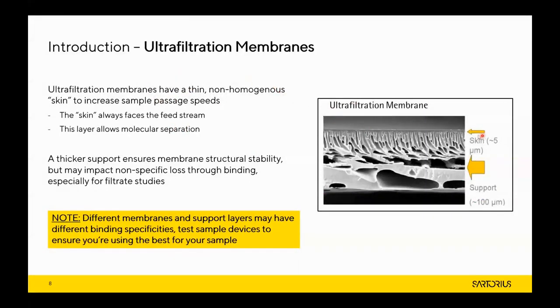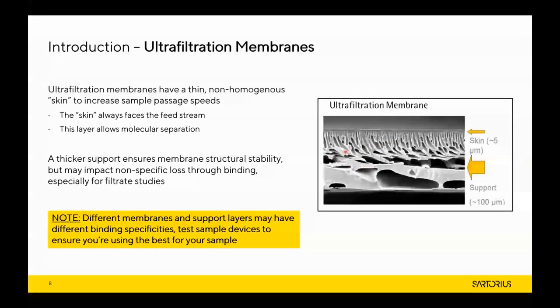The skin layer — approximately five micrometres thick — is where separation actually occurs, and it's very important that this always faces the feed stream. The thicker support provides structural stability, but it can contribute to non-specific binding since it's typically a non-woven polyester or cellulose. So when assessing compatibilities, consider not just the skin layer (regenerated cellulose or polyethersulfone) but also the support layer, particularly for filtrate studies. It's always good to test sample devices when optimizing or working with a new molecular target.